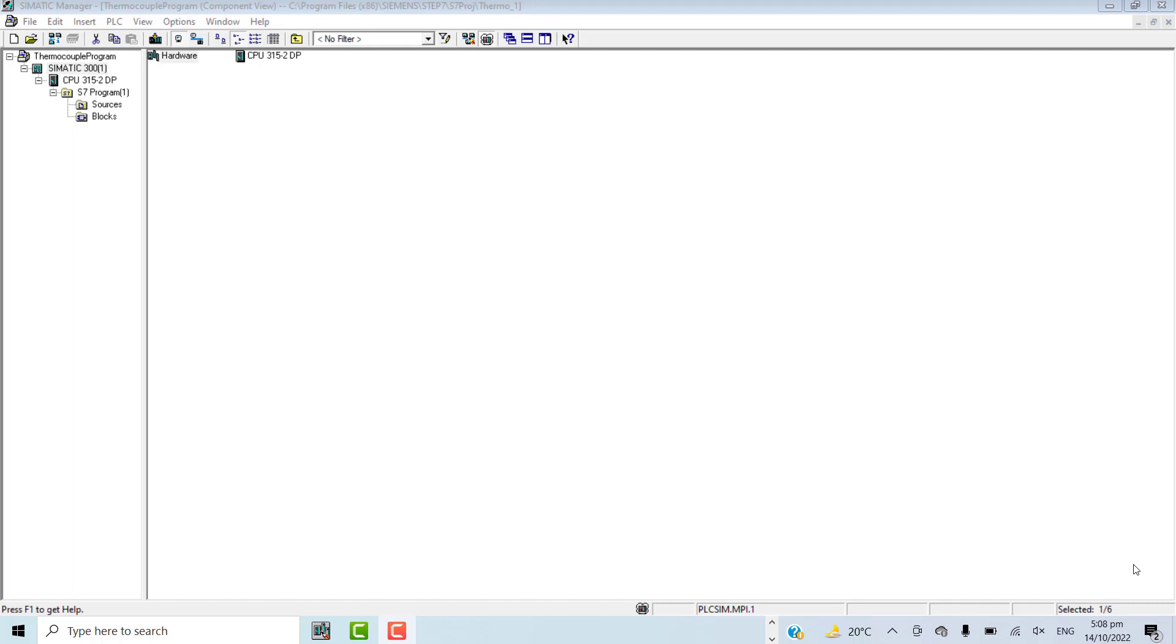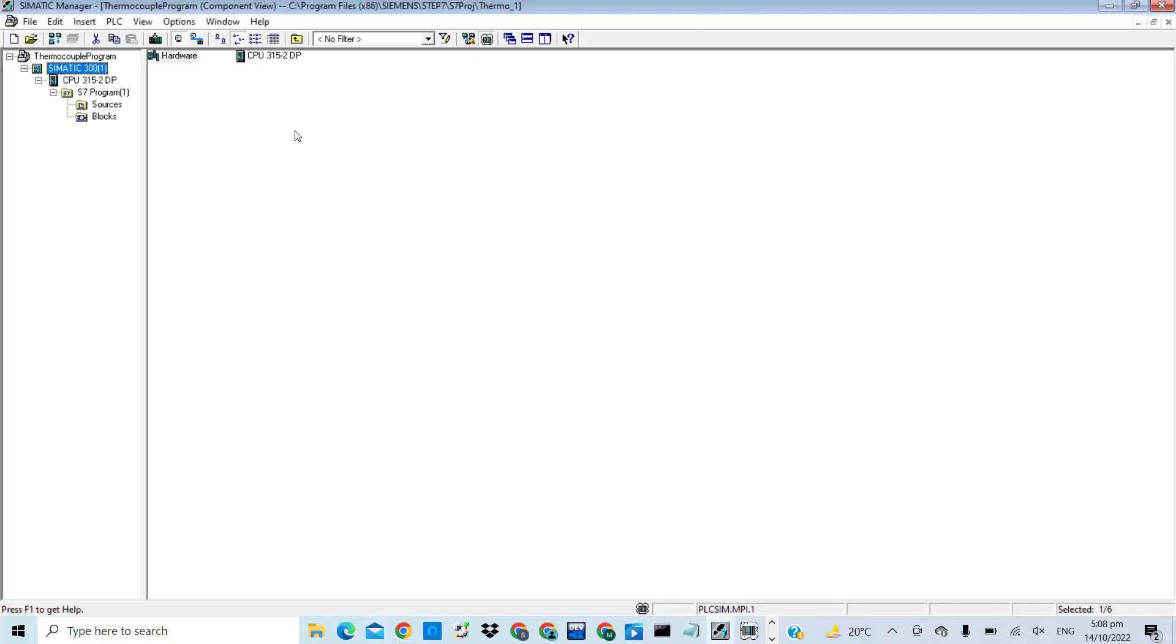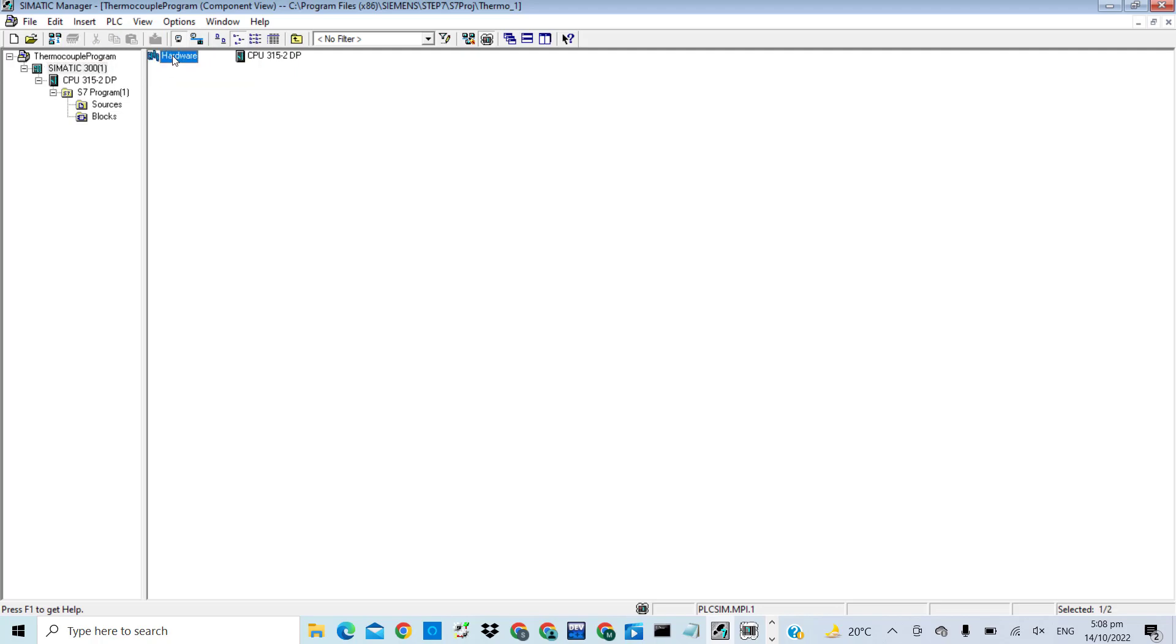For example, if you have a problem with your Siemens PLC, I will open the Simatic Manager and first of all go to my hardware configuration. I will try to go online to watch the online status of my PLC CPU and its respective modules.